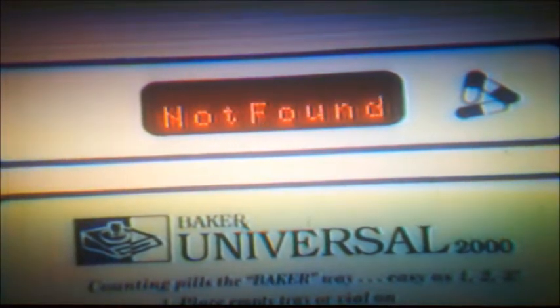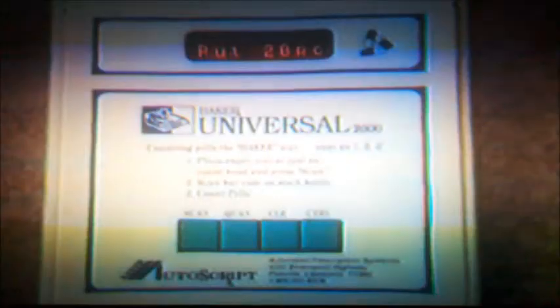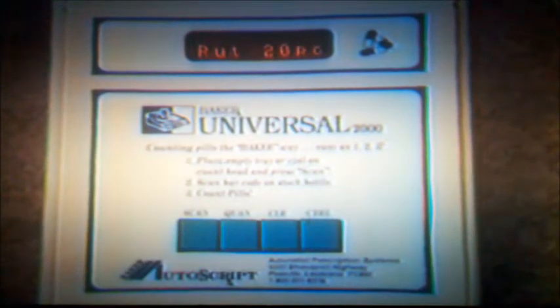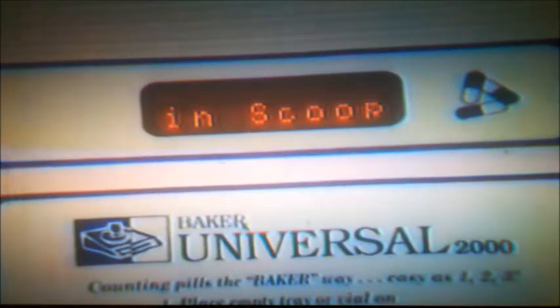If a certain drug type is not in the library, a Not Found indication will be displayed on the scanner unit when the barcode is scanned. The display will ask you to put in 20 tablets into the scoop or vial. Simply count 20 tablets or capsules on your counting tray and put them in the container all at one time.